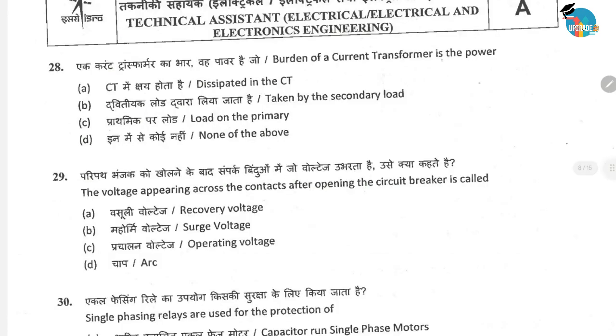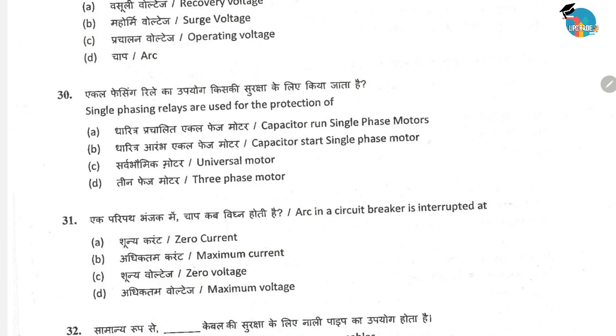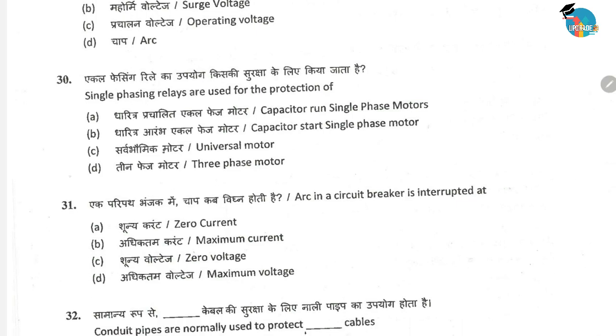Next question is burden of a current transformer is the power. So it is the power taken by the secondary load. Correct answer is option B. Next question is the voltage appearing across the contacts after opening the circuit breaker is called. So the voltage which appears after opening of the circuit breaker is called the recovery voltage. Single phasing relays are used for the protection of. The single phasing relays are always used for the protection of a three-phase motor. Next question is arc in a circuit breaker is interrupted at. So arc in a circuit breaker is interrupted at zero current. Correct option is option A.